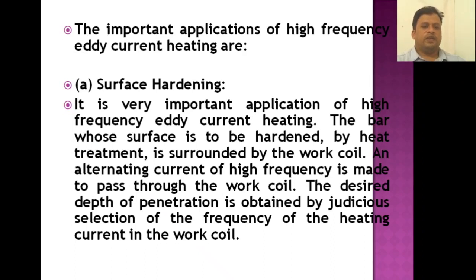The bar whose surface is to be hardened by heat treatment is surrounded by the work coil. An alternating current of high frequency is made to pass through the work coil. The desired depth of penetration is obtained by judicious selection of frequency of heating current in the work coil. So, this surface hardening is also one of the applications where high frequency eddy current heating is required.